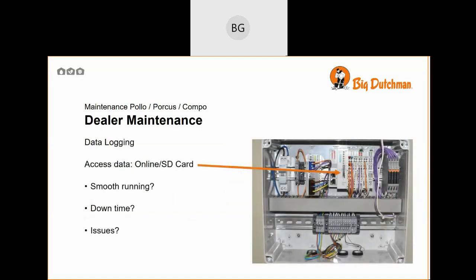For the data logging, access the data either online or by reading the data that is on the SD card. Has the machine been running smoothly? Has there been any downtime? Have there been any issues? You may notice that the conductivity has been rising and suddenly falling, rising and suddenly falling. This is correct. However, if it's suddenly the same for 2 weeks, or it has been the same for 3 weeks' time, then there is an issue. It's not recording correctly, or the conductivity isn't rising as it should.